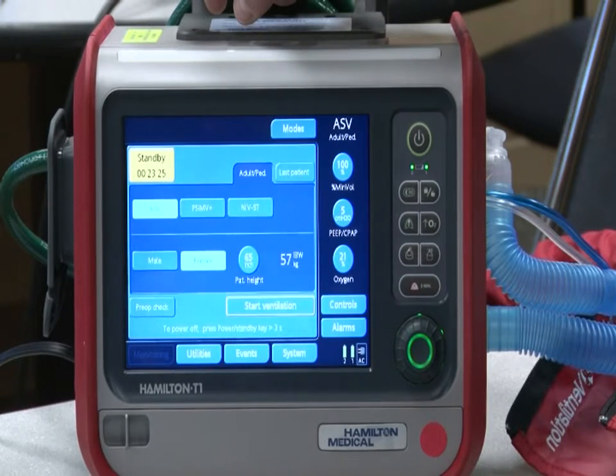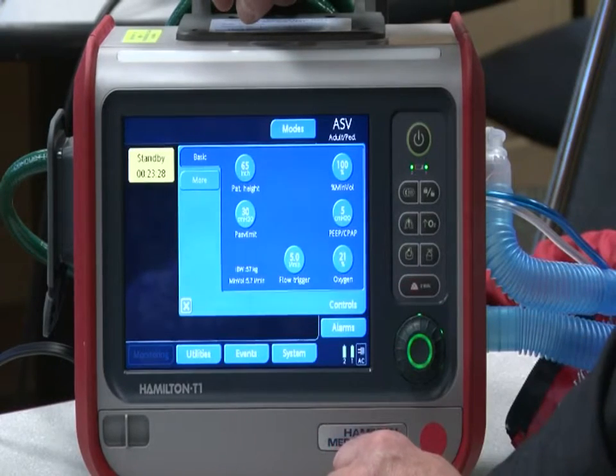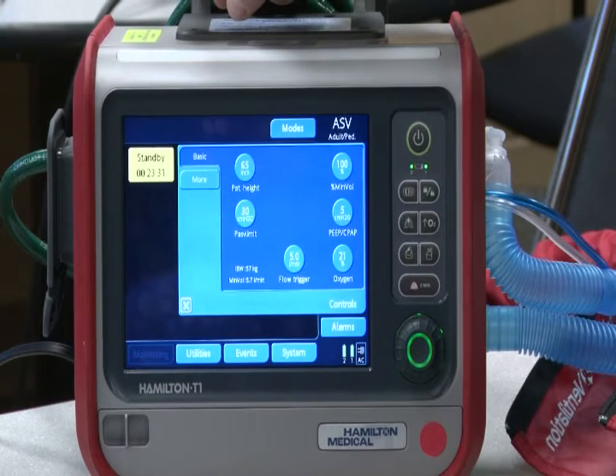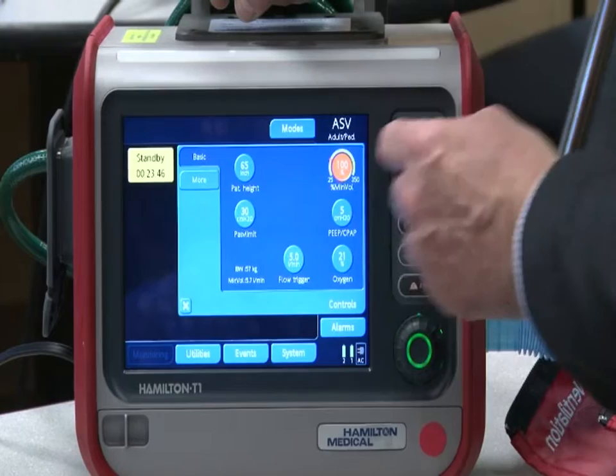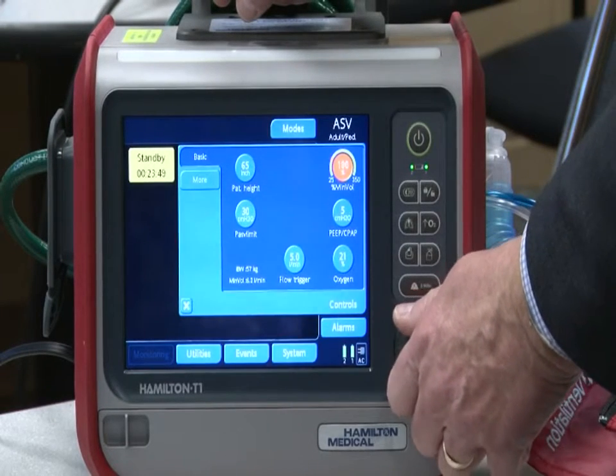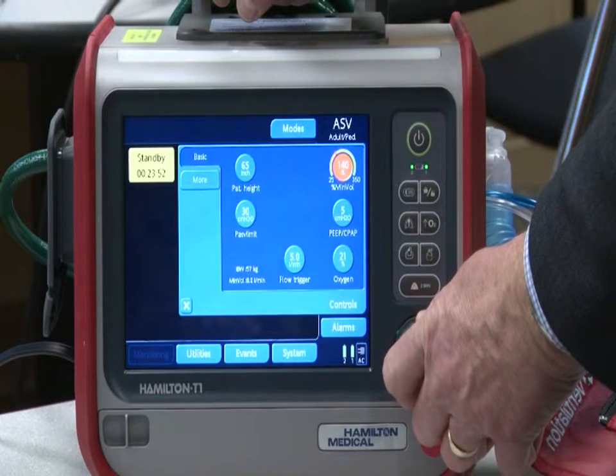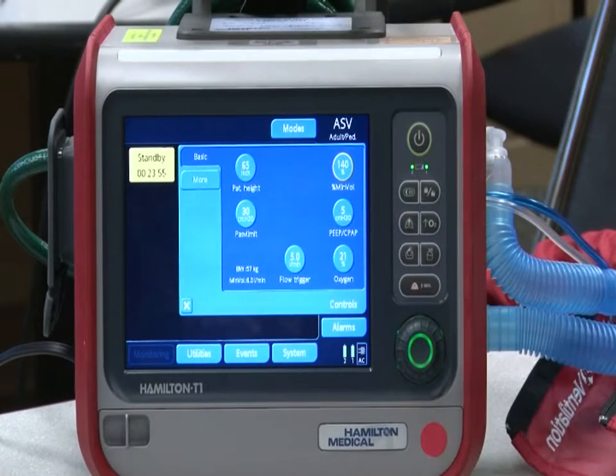Okay, so if we go back to the controls tab, what if that patient was already on another ventilator and was already receiving an 8 liter per minute volume? We wouldn't want to put them on the T1 on ASV and transport them at a lower minute volume because they'd become hypercarbic, right? So with the control tab open, activate that percent minute volume, and I want you to turn the knob clockwise until you get an 8 liter minute volume, and then tell me what that percent minute volume is now. So if you did it right and you didn't change the patient along the way, you should say 140%, and the minute volume should now be 8 liters a minute.